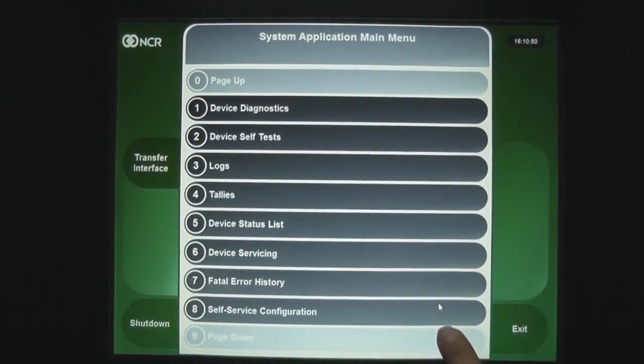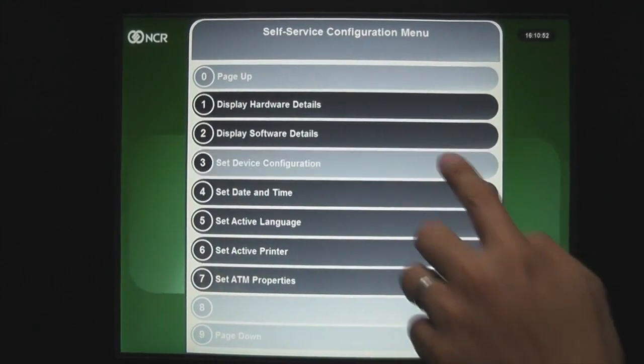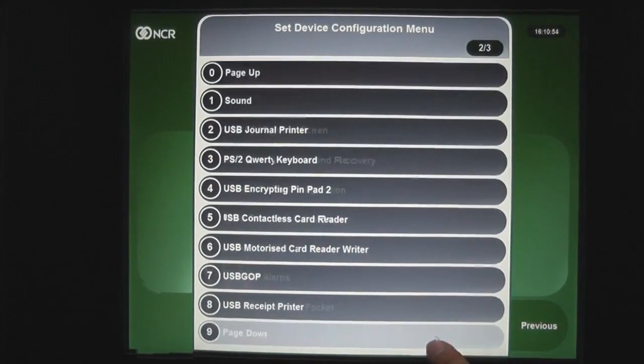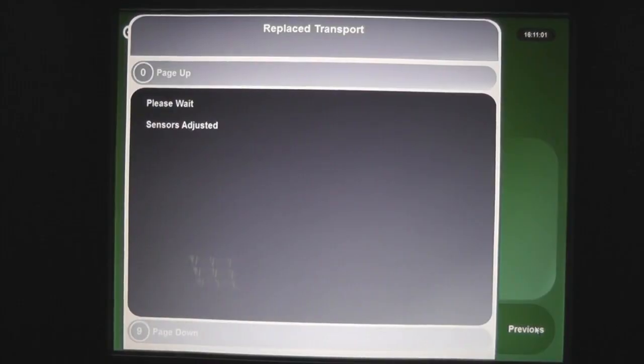After replacement, the transport sensors must be calibrated. In the SysApp Set menu, run a Replaced Transport command for the intermediate transport to calibrate the sensors.